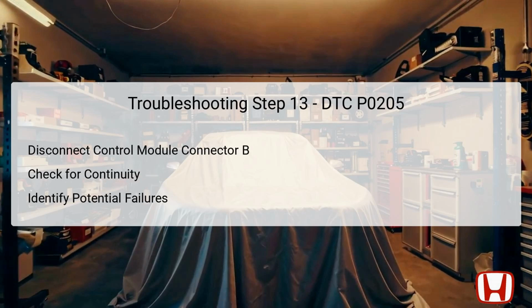During step 13, your goal is to disconnect the injector control module connector B and perform continuity tests between specified test points. This step aims to ensure there are no interruptions in connection that could result in injector circuit failure. If continuity is confirmed, proceed to step 16. If there's no continuity, this suggests potential wiring issues or faults in the circuit that require repairs to maintain proper injector functionality.